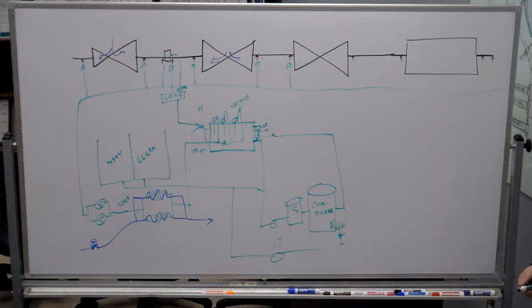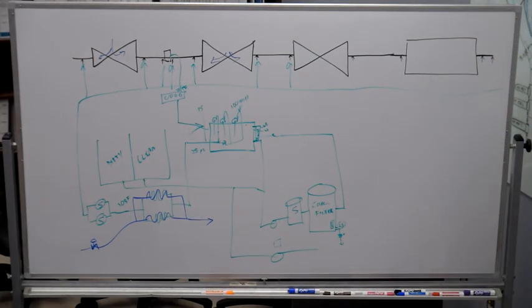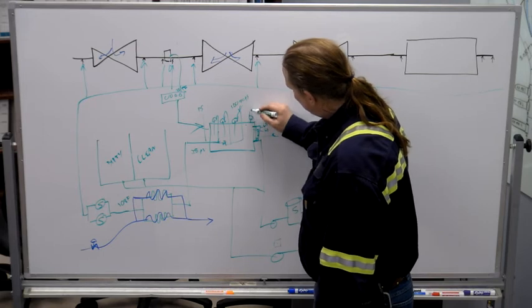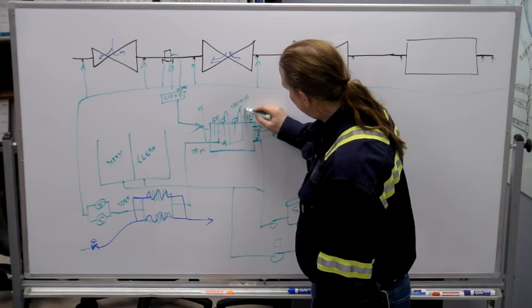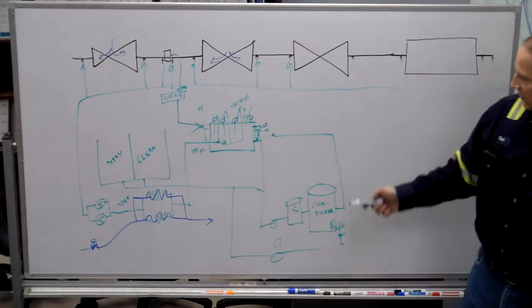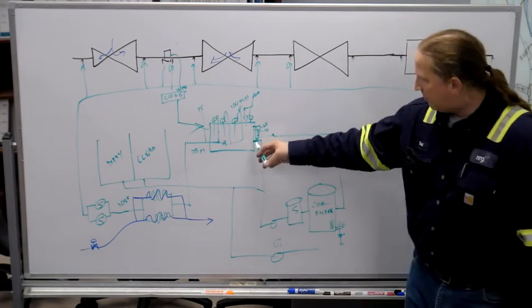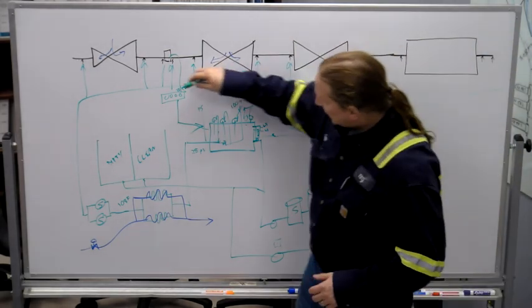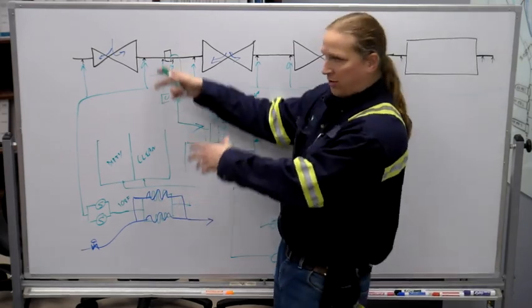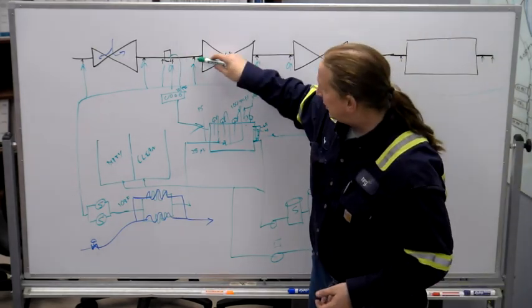They do oil samples and send them off. And other than that, during the outage, there's a big swap out all the oil thing. And I don't know if that's every outage, that might be every three years or something. And other than that, like maybe once or twice, we've had to actually add oil. That low oil switch came in because all the drips added up. And there's the vacuum, the vaporizer. What am I looking for? Extractors. Extractors, yeah, extractors. So these are blowing out the roof. And they are pulling a vacuum on the tank. And because of the way the drain system works, it keeps that entire drain system under a vacuum. So if you do not have a couple of inches of vacuum on that tank, then you will have an oil mist at the bearings.